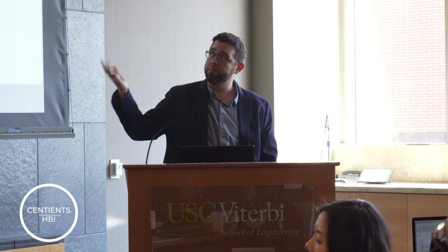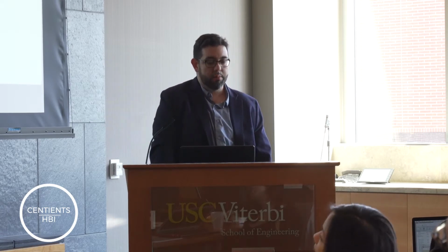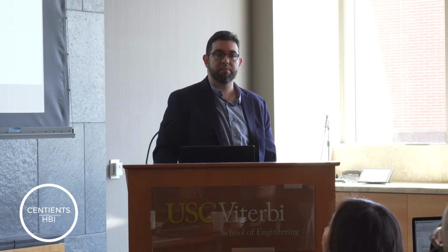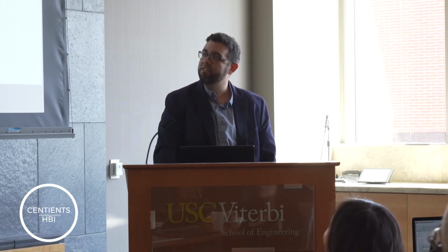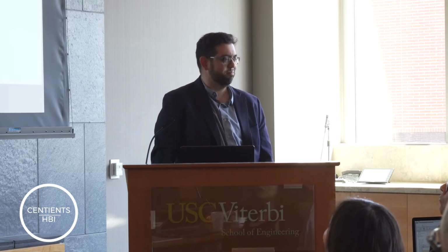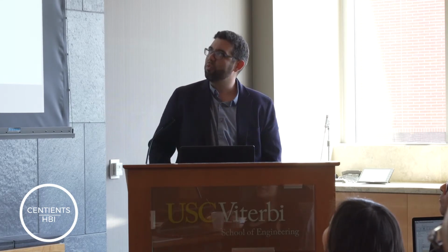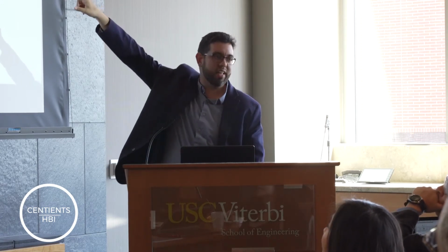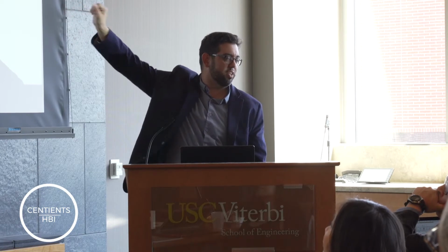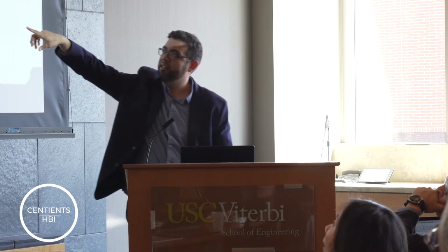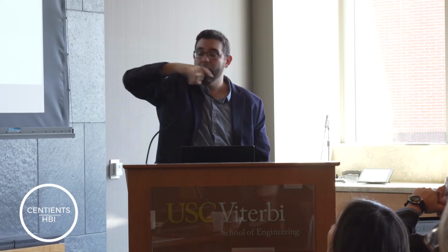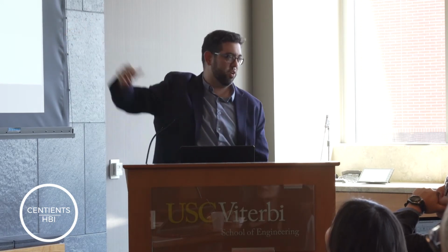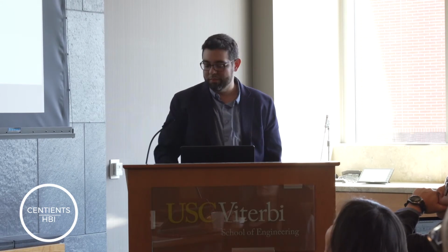We ran it in a very old building at UC Berkeley. Actually, this building has 15 different HVAC systems in it that don't talk to each other. And so we expected we would find lots of awful things happening. And of course we did. We found a chiller that was dysfunctional, a hackathon that happened on the weekend, which changed the energy consumption profile, and competing heating and cooling systems going on for 18 days, actually. So when we alerted the building manager about this, it was quickly identified and addressed.